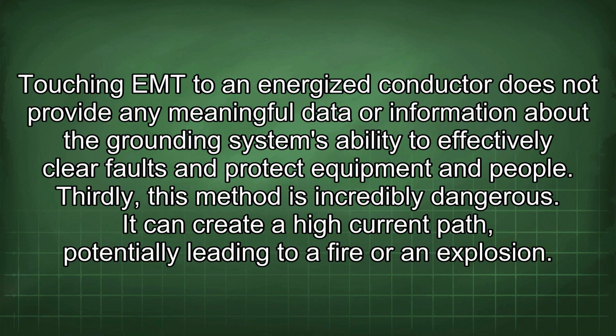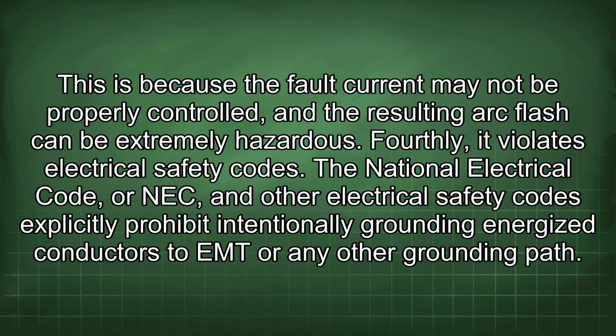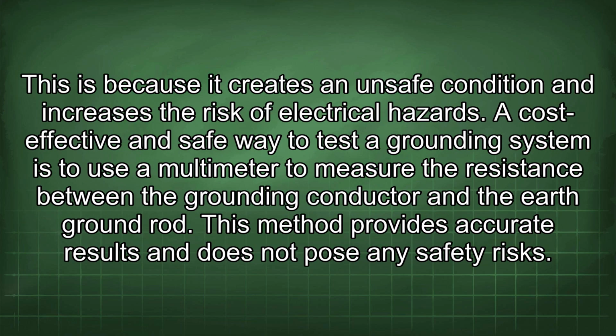Thirdly, this method is incredibly dangerous. It can create a high current path, potentially leading to a fire or an explosion. This is because the fault current may not be properly controlled, and the resulting arc flash can be extremely hazardous. Fourthly, it violates electrical safety codes. The National Electrical Code, or NEC, and other electrical safety codes explicitly prohibit intentionally grounding energized conductors to EMT or any other grounding path. This is because it creates an unsafe condition and increases the risk of electrical hazards.